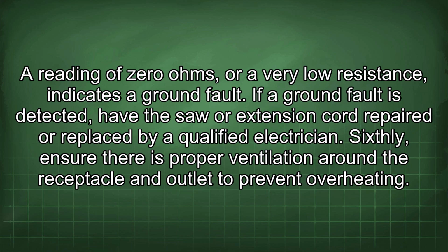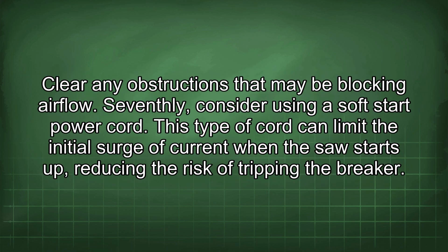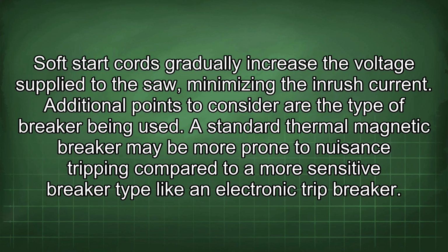Sixthly, ensure there is proper ventilation around the receptacle and outlet to prevent overheating. Clear any obstructions that may be blocking airflow. Seventhly, consider using a soft start power cord. This type of cord can limit the initial surge of current when the saw starts up, reducing the risk of tripping the breaker. Soft start cords gradually increase the voltage supplied to the saw, minimizing the inrush current.